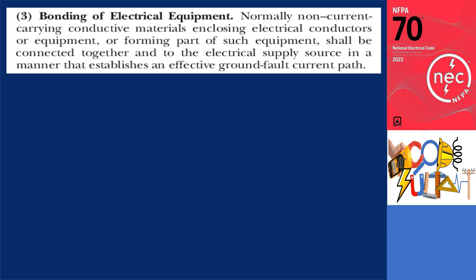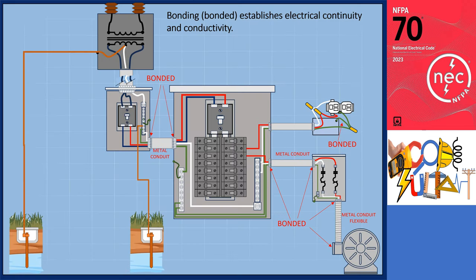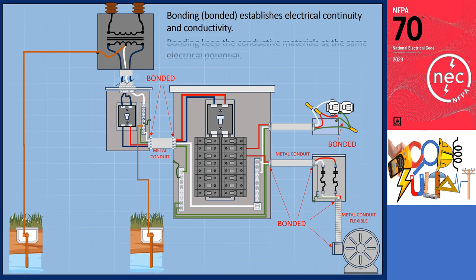Section 250.4A3 — Bonding of Electrical Equipment — states that normally non-current carrying conductive materials shall be connected to the electrical supply source in a manner that establishes an effective ground fault current path. Electrical bonding involves connecting metallic objects that may contact electrical faults or induced voltages to grounding conductors. Panelboard enclosures are bonded to metallic conduit and linked to the ground terminal, establishing an effective ground fault path, ensuring excessive current flows safely through bonding and grounding conductors. Bonding non-current carrying conductive parts together also keeps them at the same electrical potential, eliminating shock hazards between bonded enclosures.